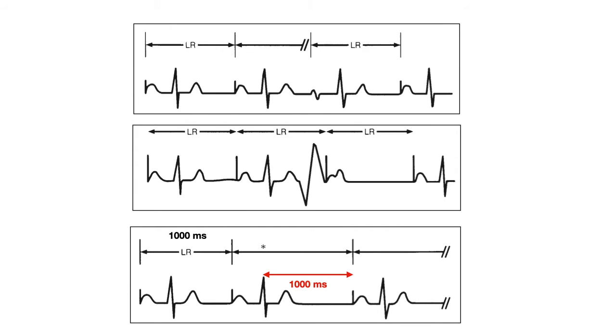In the AAI mode, the timing cycles consist of a programmed lower rate limit and an atrial refractory period, acting just like a VVI mode. When the timer of the lower rate limit is complete, the pacing artifact will be delivered in the atrium in the absence of any native atrial activity. And if a spontaneous P wave occurs, the lower rate timer will be reset and started from that point. The atrial refractory period will begin with any sensed or paced atrial activity. In the AAI mode, only the atrial activity is sensed.